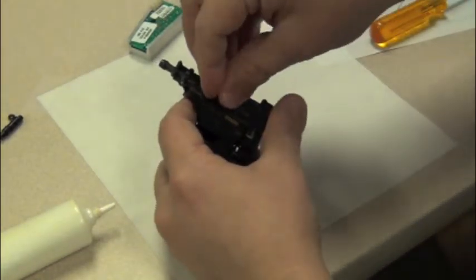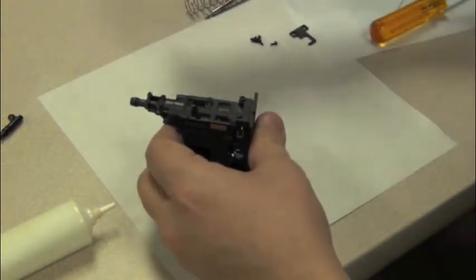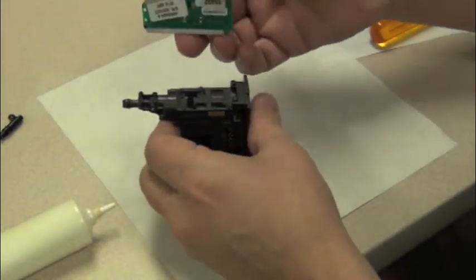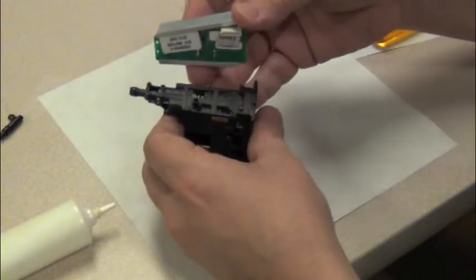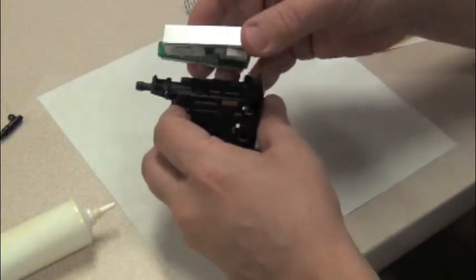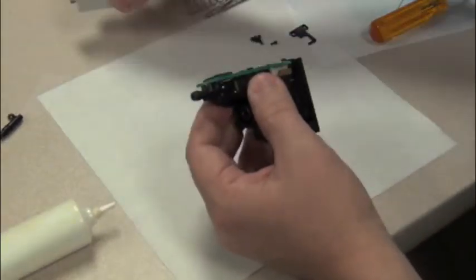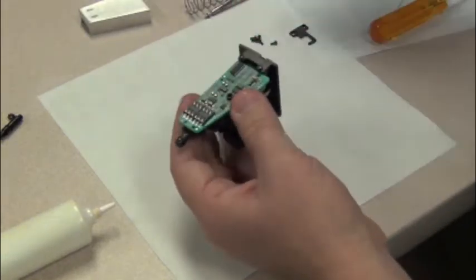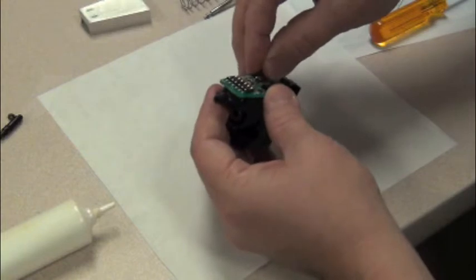Replace the silencer. Take the spindle PCA and removal tool and carefully insert the four pins into the four holes in the valves. Slide the tool out. Place the three screws back in the spindle PCA.